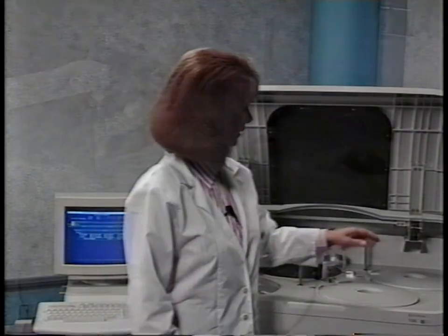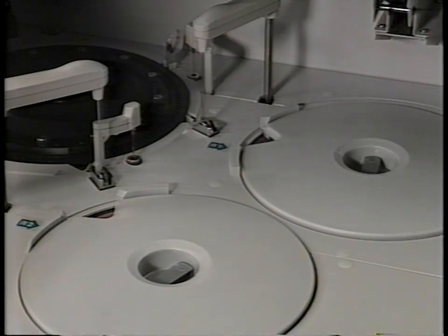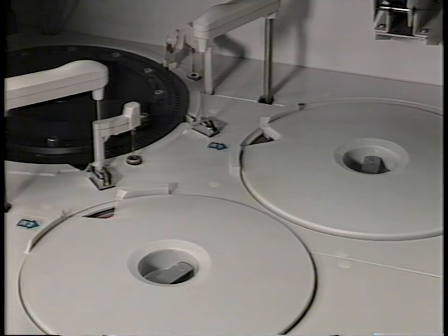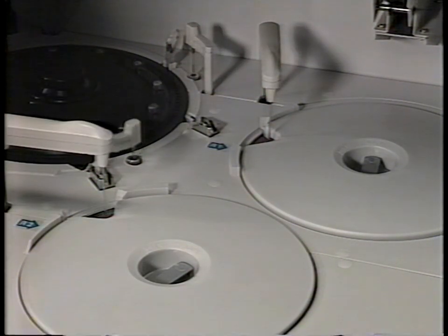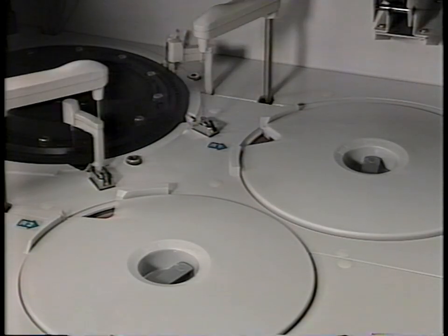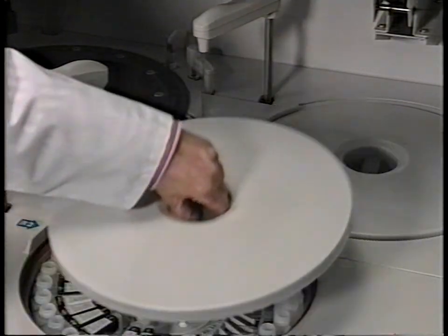Let's take a look at the photometric reagent dispensing system. A few tests use only one reagent, which we refer to as the T1 reagent. Many tests use an additional reagent dispensed at T2 or T3 timing. Other tests may use a fourth or T4 reagent. T1 and T4 reagents for each of the 46 channels are stored in this reagent disc. And T2 and T3 reagents are stored in this disc. Their compartments are refrigerated and they're under locking covers, which helps prevent evaporation.